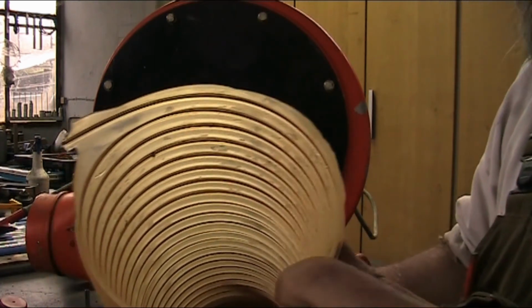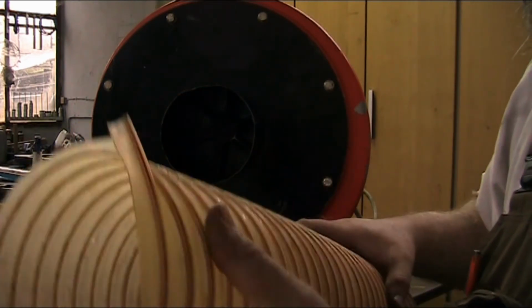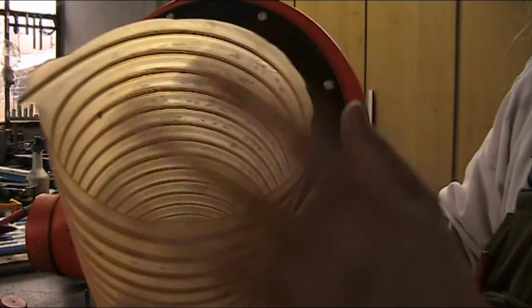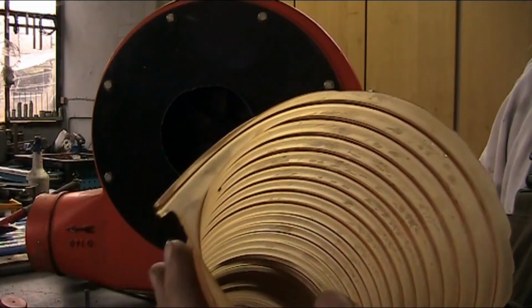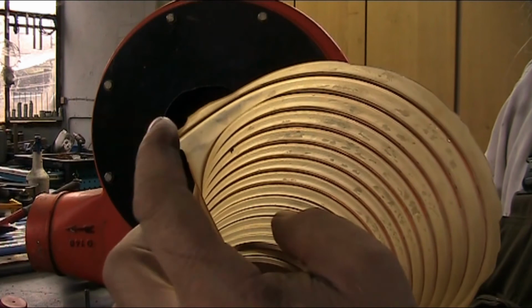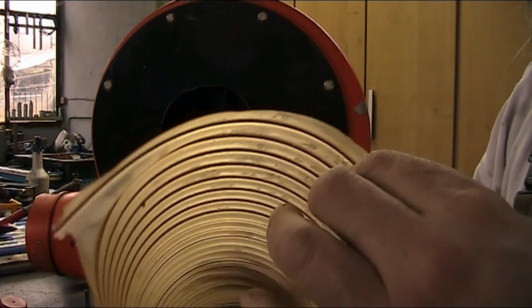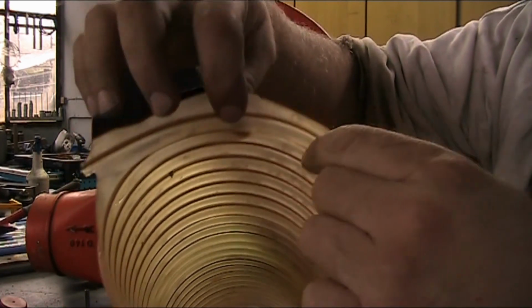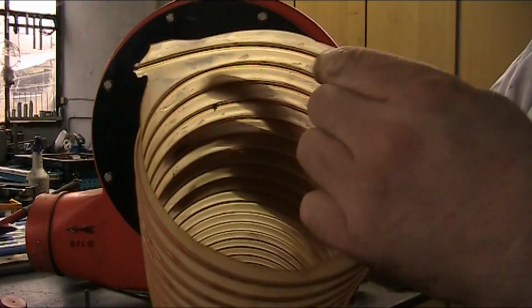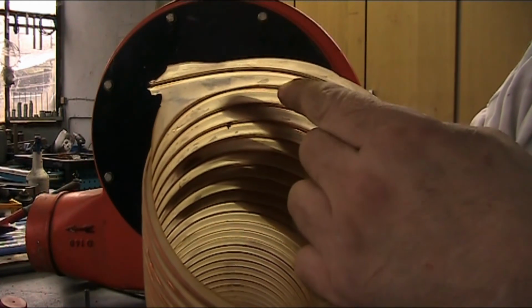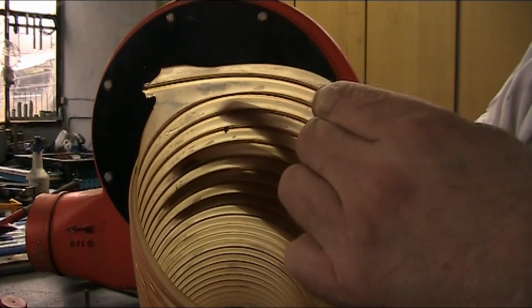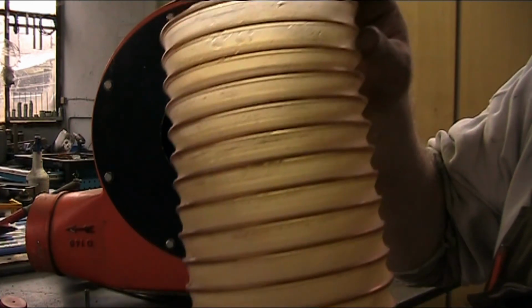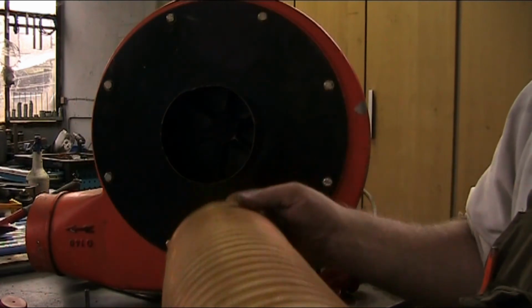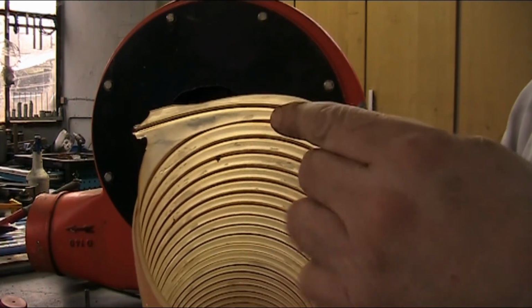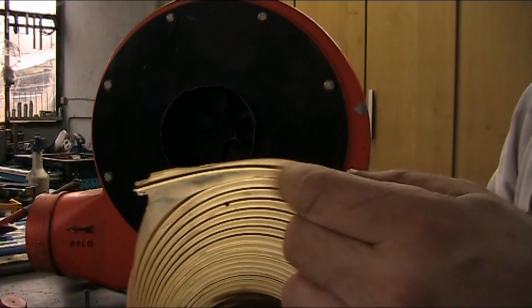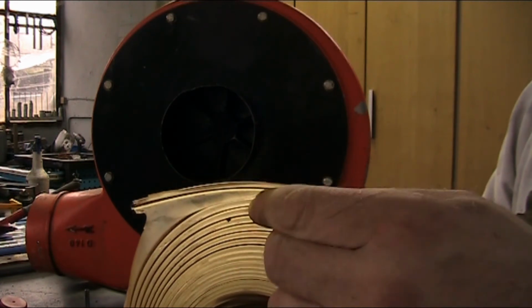So here we have our flex tube, and as you notice, there's a metal spiral in here, and when you cut it, of course, sometimes this kind of thing happens. So how do you ground this? Well, it's real simple. When you go in here, just scrape off a little bit of the covering on this wire to where you get it bare on both ends, to where it attaches to the machine, i.e. your table saw, your bandsaw, what have you, and the blower. Just scratch it off a little bit, and you can get a good ground that way.